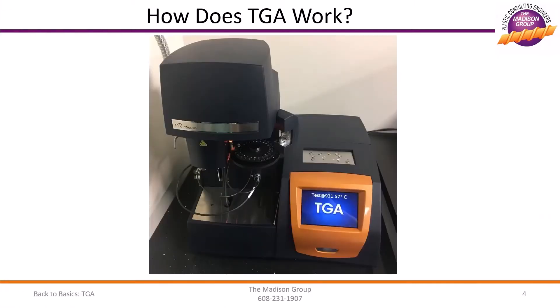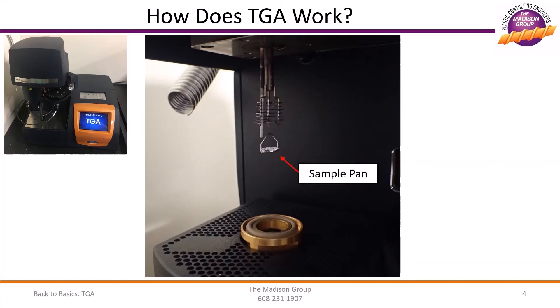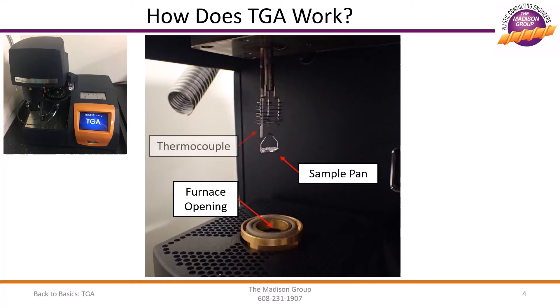This is a thermogravimetric analyzer. At its most basic, a TGA subjects a relatively small sample of material to a temperature and atmosphere and measures the weight changes of the sample. The most common TGA experiment involves heating the sample to a high temperature so that the organic matter of the sample decomposes. For analysis, the sample is placed onto a hanging pan that is measured by a balance and then situated in a sealed furnace with a thermocouple that measures temperature.